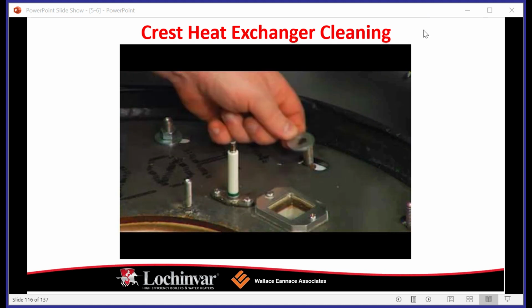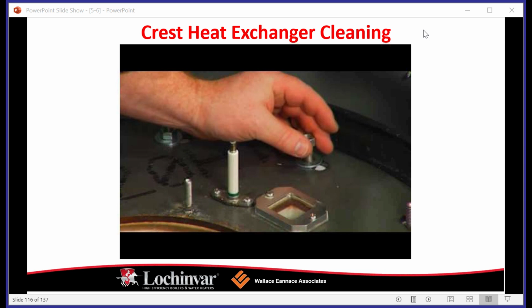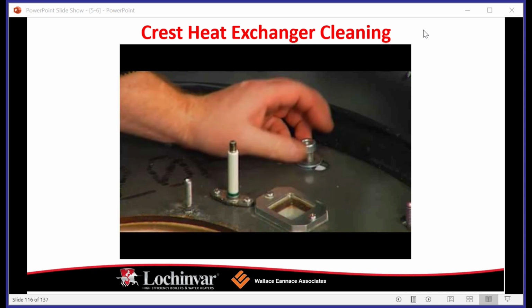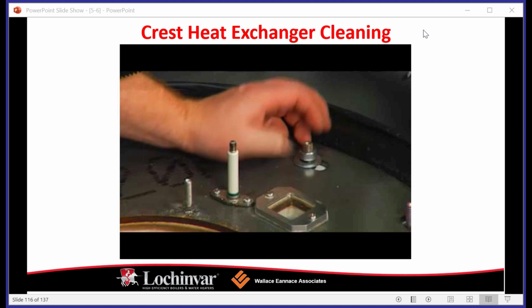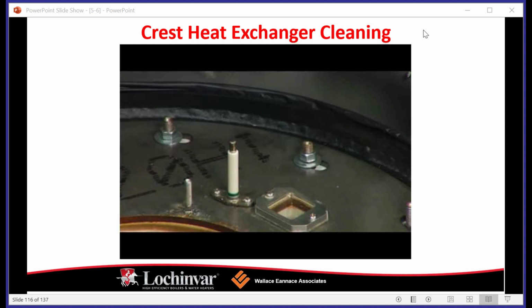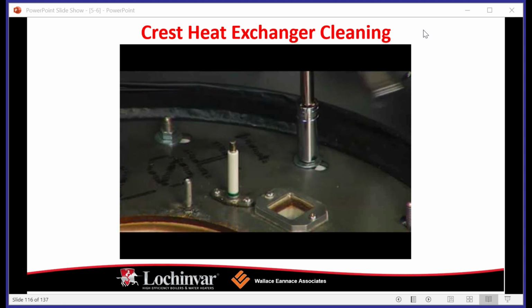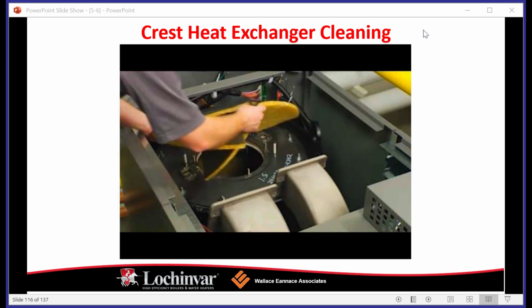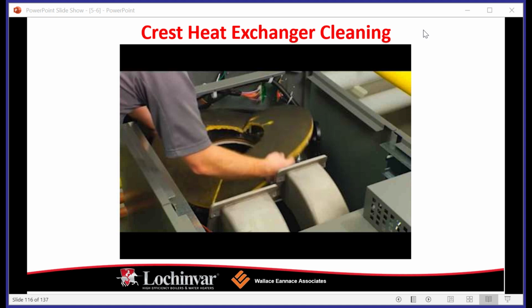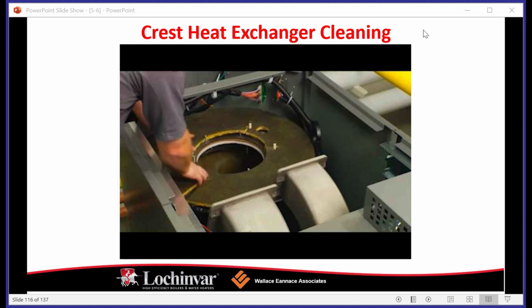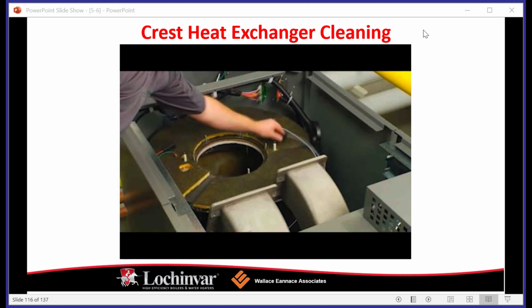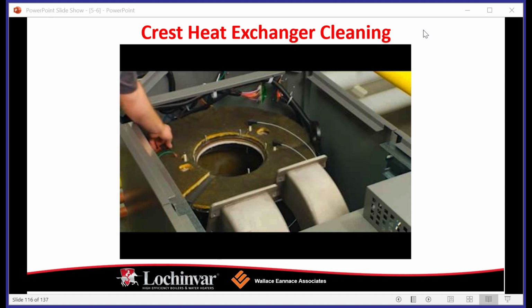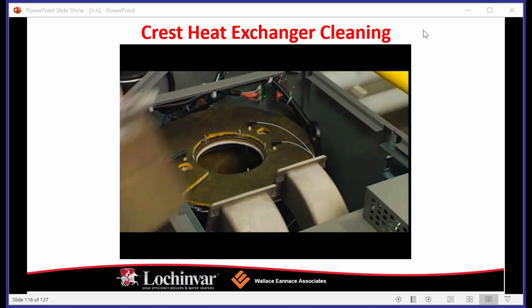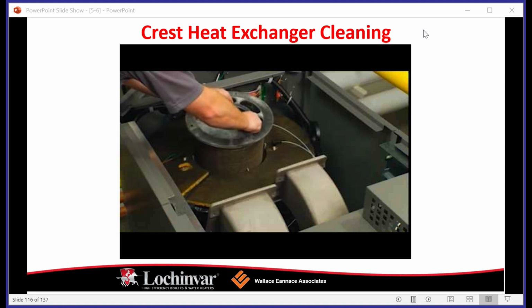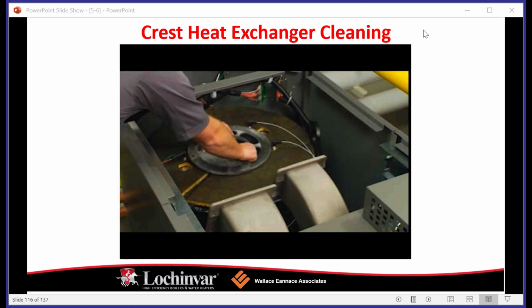Remove the top access panel by pulling up on the handles and lifting away. Remove the 4 Phillips head screws securing the top back panel to the boiler. Remove the panel from the boiler. Remove the 4 bolts and nuts from each gas-air manifold. Remove the 5 nuts securing the gas-air manifold to the burner. Carefully lift up and remove the gas-air manifold from the burner.